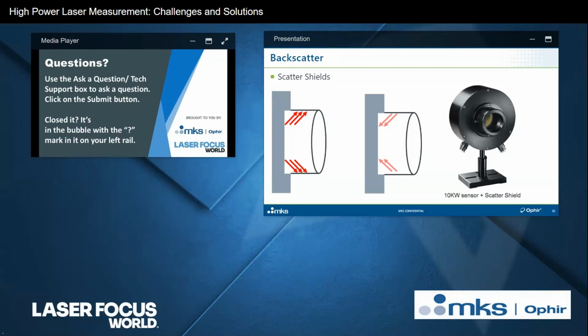Obviously, for the same power, the sensor is going to be absorbing more, which means that the meter is going to need to know, quote unquote, that the scatter shield has been added. There needs to be a separate calibration factor for the scatter shield condition to make sure that the reading is correct, even though much more of that beam is in fact being absorbed.